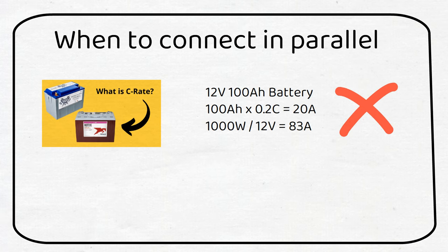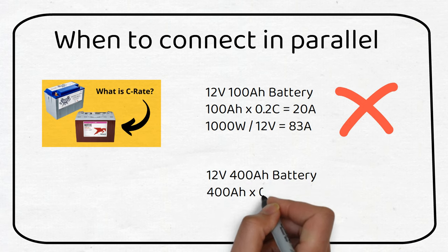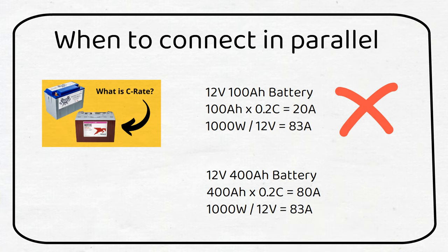It's much better to have 4 batteries in parallel if you've already bought your 12 volt inverter. Otherwise the voltage of the battery should be increased. Let's use 4 batteries in parallel and do the same calculation. 400 amp hours times 0.2C is 80 amps. We can see that 80 amps is about what the inverter will draw. This is a better configuration.